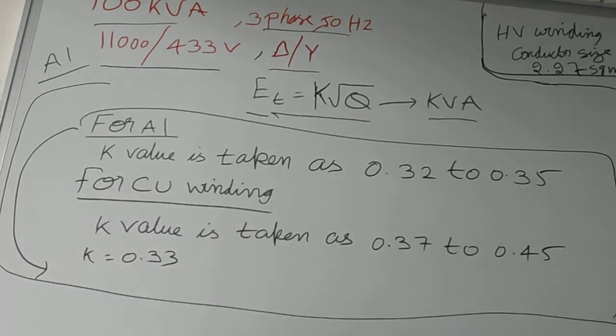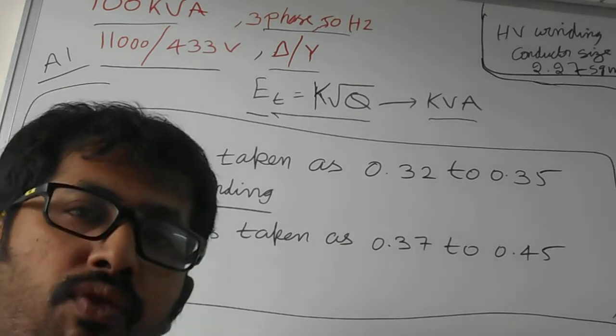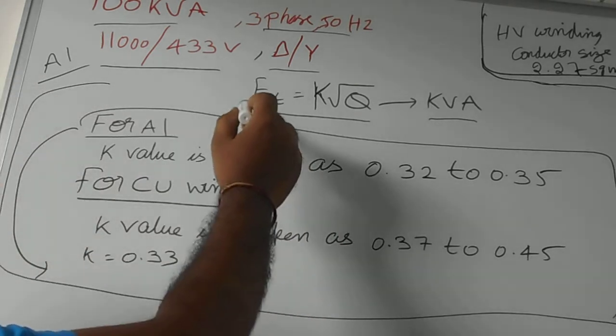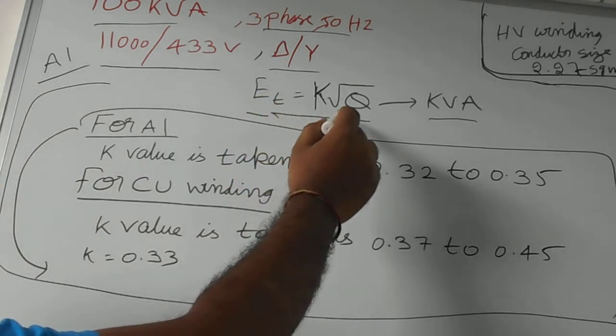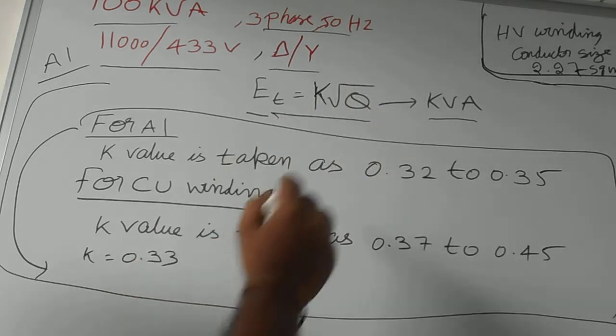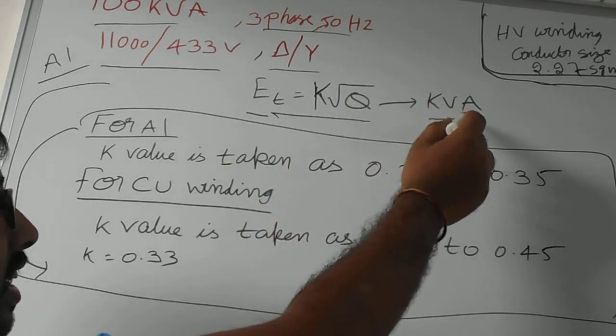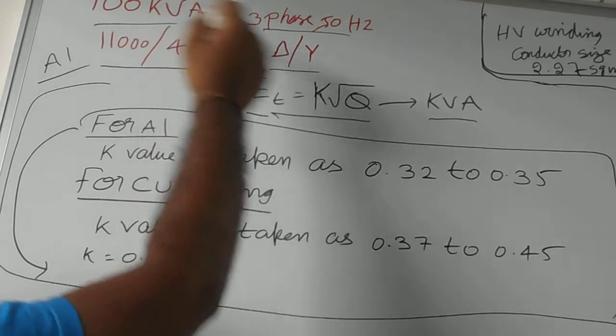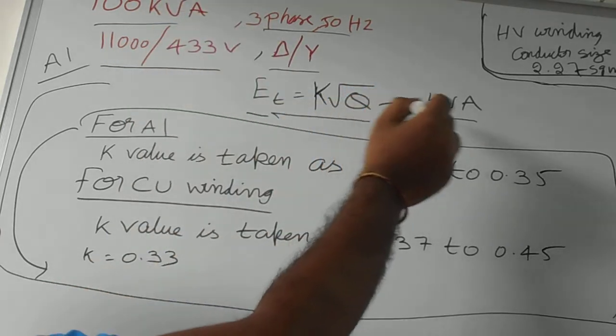Before finding that calculation we have to know the basic formula that is EMF per turn is equal to K into root of Q. So what is Q? It is a kVA rating. For example, we are taking 100 kVA, we have to substitute the root value of 100 kVA.